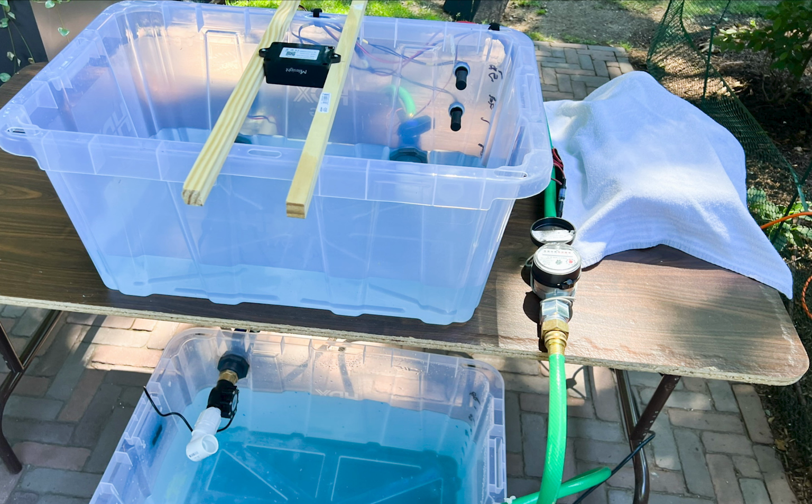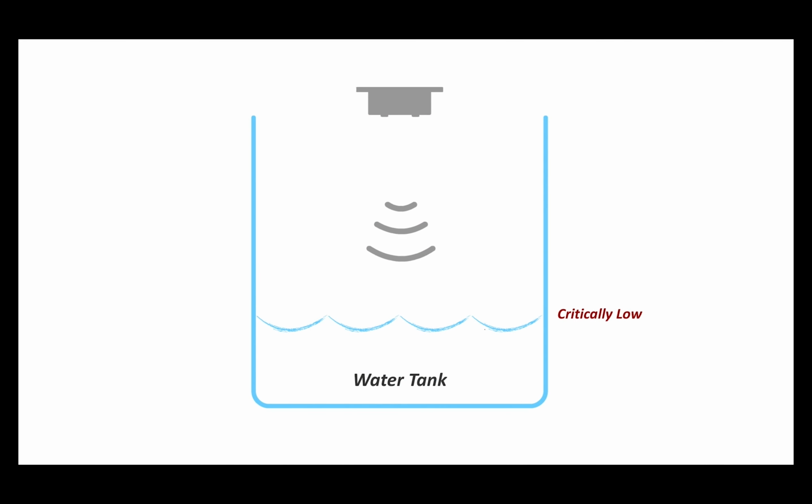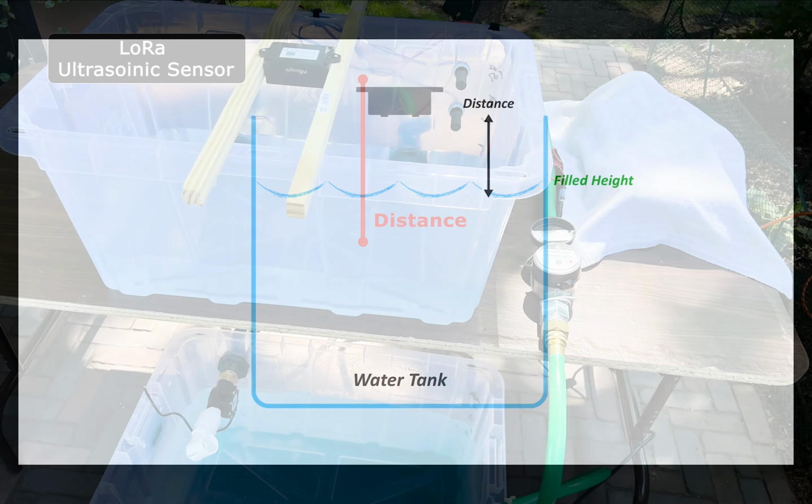Now we're going to look at various ways to monitor pilot sites. Let's start with water tank monitoring. One device that can be used, which we demonstrated in the first video, is a low-cost ultrasonic sensor positioned at the top of the tank, looking downward facing the water. It's able to measure the tank fill level and send data back periodically, say hourly or once or twice a day, to the dashboard. The sensor works by emitting an ultrasonic wave towards the water, and it measures the time for the wave to reflect back and be received. The longer the time, the farther the distance.